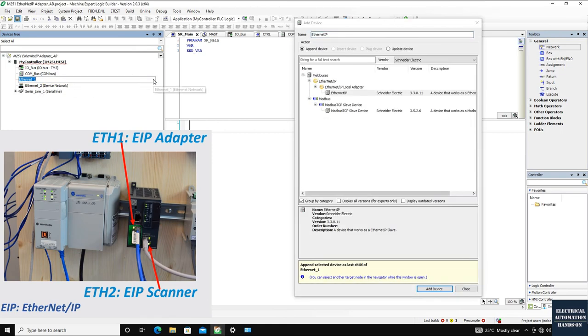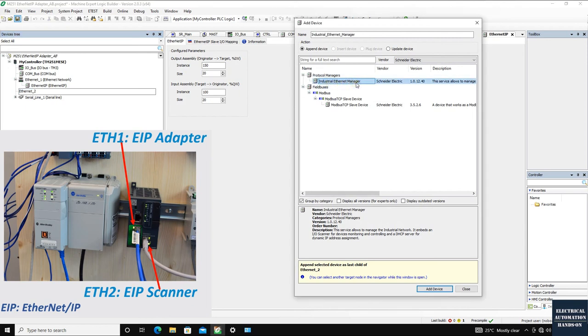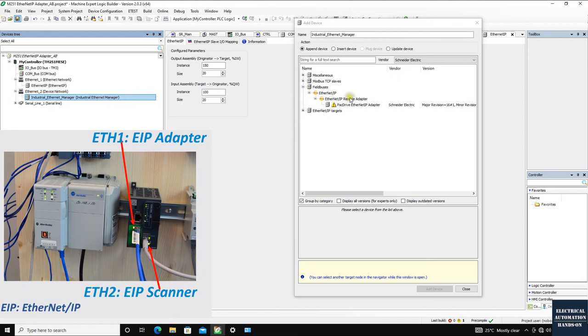When we click Add on port 1, it provides two functions: EtherNet/IP adapter and Modbus TCP. We'll add the EtherNet/IP function. Note that for Ethernet port 2, which can run as an EtherNet/IP scanner (master), you first need to add an Ethernet Manager, then you can add other EtherNet/IP adapter devices. These two ports have different roles — keep that in mind.